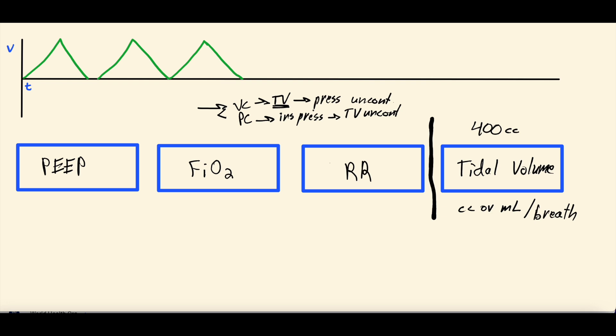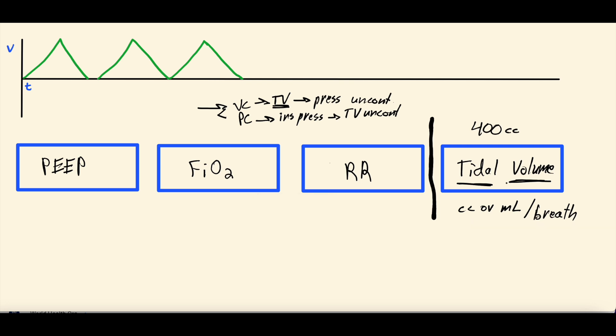What makes volume control different from pressure control is that you're setting a tidal volume you want the patient to get with each breath. Ventilators are smart — the patient has some control because the ventilator isn't just rigidly pushing that volume in regardless. There will be some variability from breath to breath depending on whether the patient is accepting that breath. But about this tidal volume, the patient will get with each breath, and that affects our scalars.